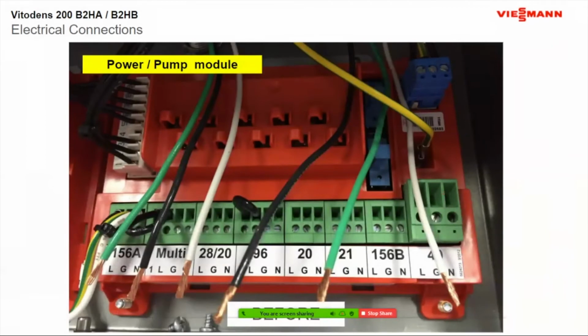Normally, when you come in for wiring the boilers, I disconnect all the wiring on the boiler, and you guys come in and wire in all the boilers. So I just take pictures of before and after. This is what you're going to look at when you come to wire the boilers. I put a little piece of tape to let you know that this is your main power, this is going to be for your pump output, and this is going to be like your 20 output.